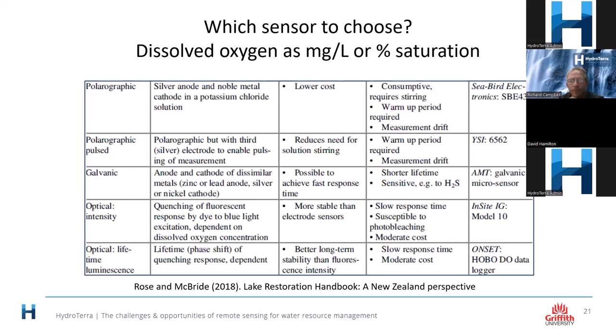All of these sensors will drift, but to varying extents. They'll have different levels of sensitivity to temperature, and there'll be different techniques used to derive the data. But one of the important things is that it's not dissolved oxygen, it's a voltage, and it's a voltage that's converted to dissolved oxygen. So we've always got to play a part in doing that quality assurance for ourselves, that our dissolved oxygen measurements with these sensors are accurate.